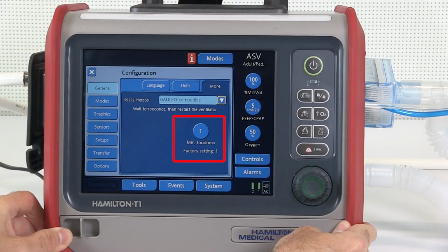Adjust the minimum loudness setting for the ventilator unit if needed. Once set, the operator of the ventilator unit cannot adjust the alarm volume to lower than the minimum loudness setting. If the alarm volume was set to less than 5 before the ventilator was turned off, it will be reset to 5 when the ventilator is turned back on. However, if the minimum loudness value is set to a value greater than 5, this will override the minimum value.